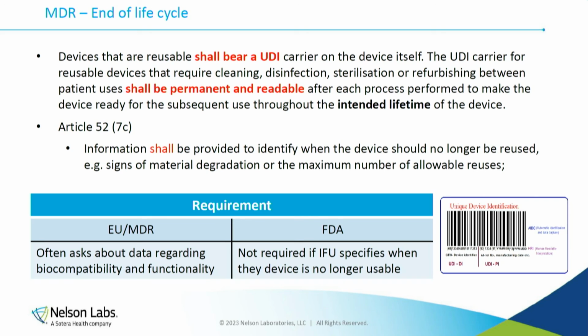Now, the UDI number. The deadline got extended to 2028, so you have time, but the UDI number has to be on the device, because that is how we're going to track how many times it can be reused. Will we be ready for it? Not the US, but will the EU be ready for it? I'm pretty sure they will be. I don't know how many people have started work on the UDI, but hopefully it is in the works, because they've extended it several times. It may be extended again, I don't know. But it needs to be on the device to make sure that it can be reprocessed as many times as you specify. And that's what ISO 10993-1 is going to start saying for biological evaluations.